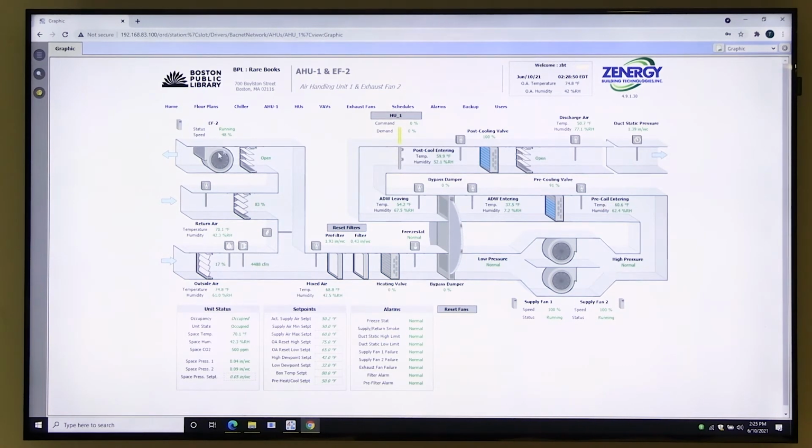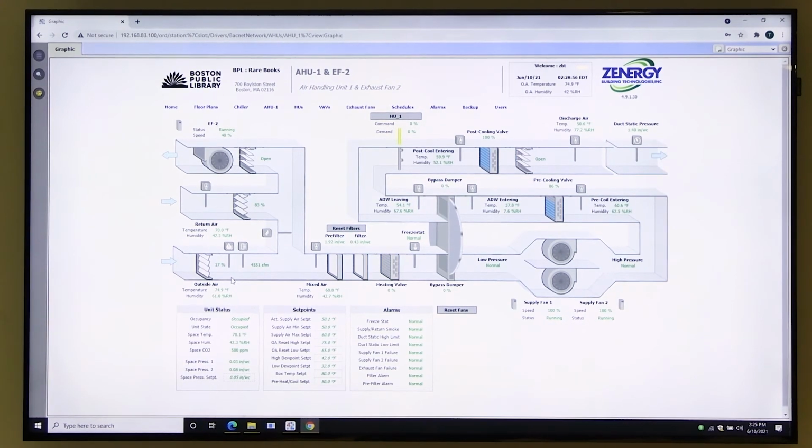So this is relieving. Because our outside air damper is at 17%, we're letting in some outside air. We're building pressure in the building. As you can see down here, we have 2 space pressure sensors, which I think is what we were looking at down on that 4th floor floor plan. As we let in more air and we're not exhausting it, our pressure builds in the space. So we need to run this exhaust fan to relieve that pressure. It's only going to run during the occupied times when we're letting in that fresh air.